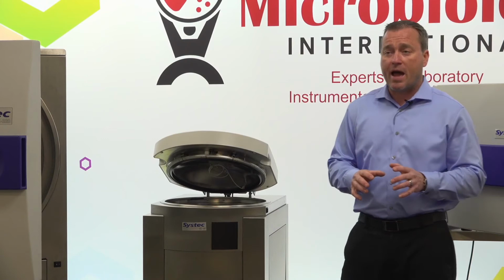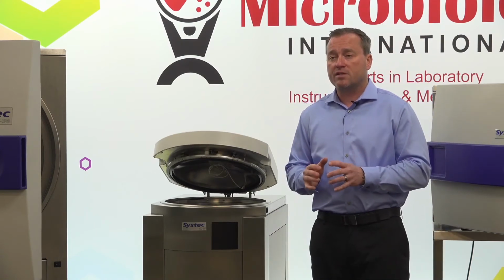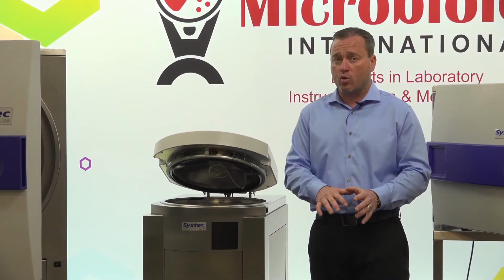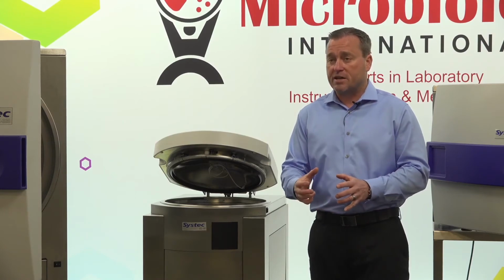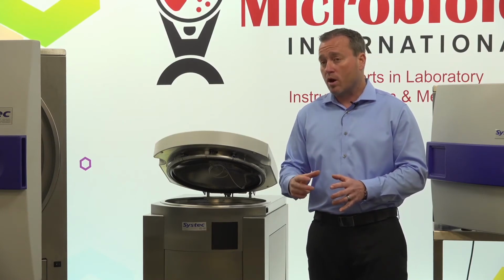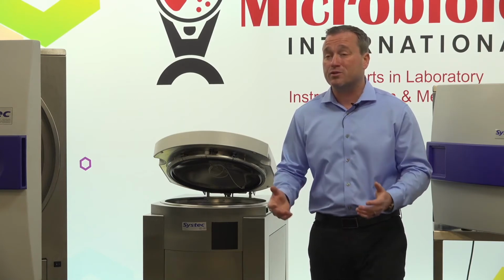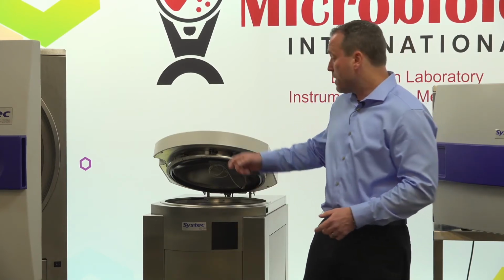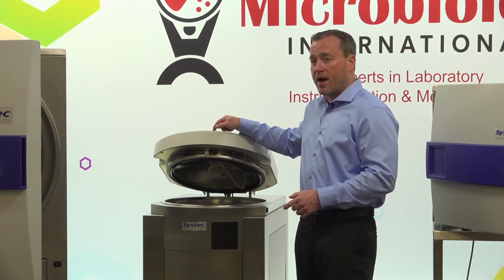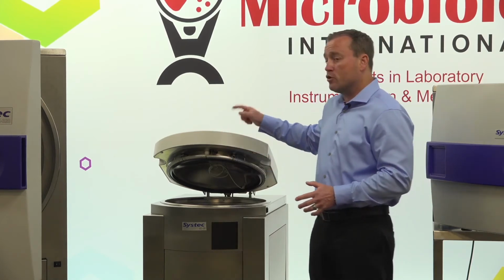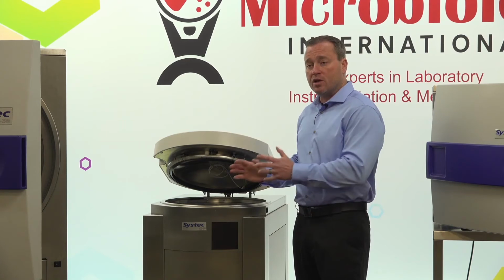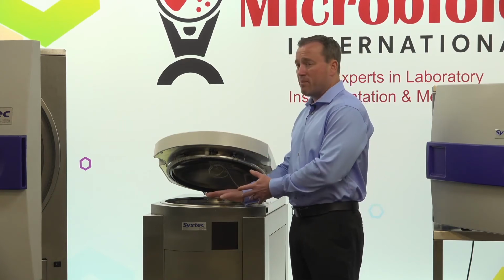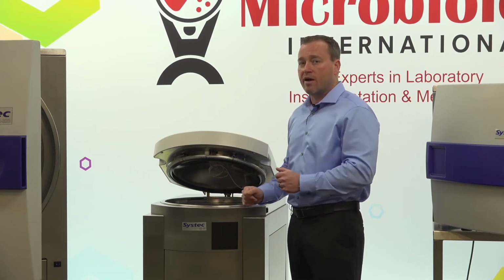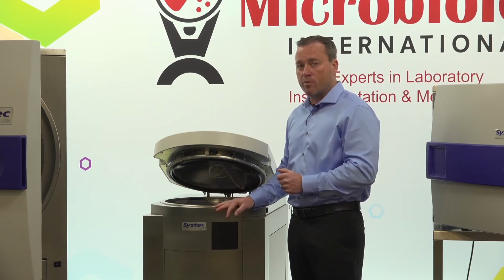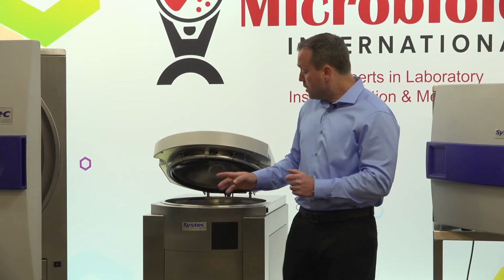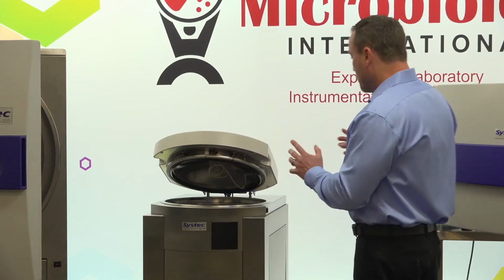Now I can also make that happen automatically. So if you do have items inside of there that are liquids that you don't mind cooling down to, potentially solidifying media, or any instruments that you just have utensils in there, something that you've been using in the laboratory, I can program this door to open automatically. So once the cycle is completed, the door would just open up, it would vent, you can come and unload the items when you want. So there may be a little bit of steam in here. If someone wears glasses, they don't have to worry about that. They can just have the instrument open directly. Okay. So the V and D series autoclaves, we'll switch to the D series now.